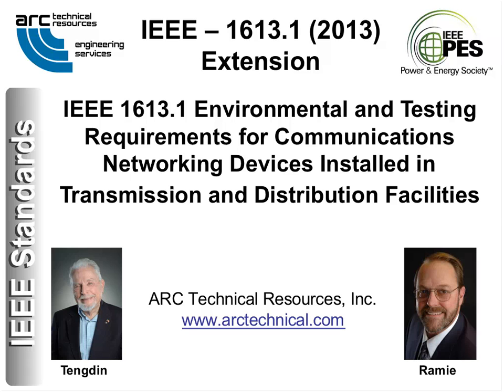We did not cover earthquake or flame. We didn't cover environmental at all. In fact, now even in the SGIP, it's still controversial to talk about EMI because it's considered an environment. An environmental resistance, you might say, like temperature or humidity or shock or vibration. But it's closer to cybersecurity in that it has fairly poor metrics, but it's system critical and you know it when you don't have it. So NEBS only applies to telephone equipment, and this is utility equipment.